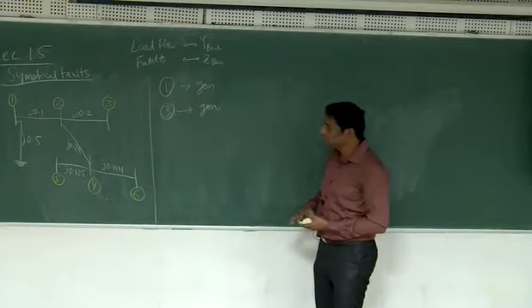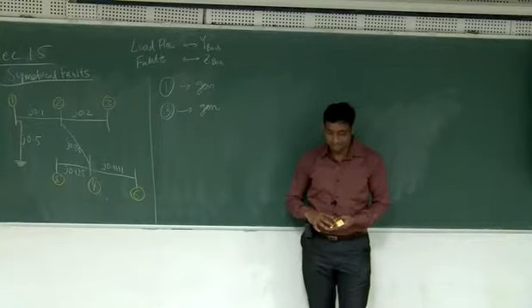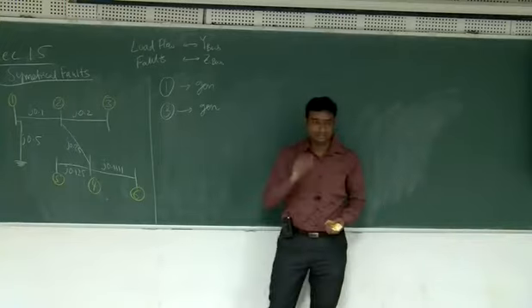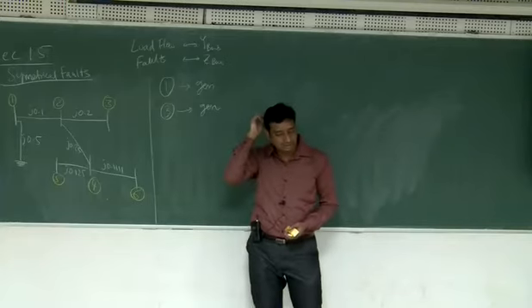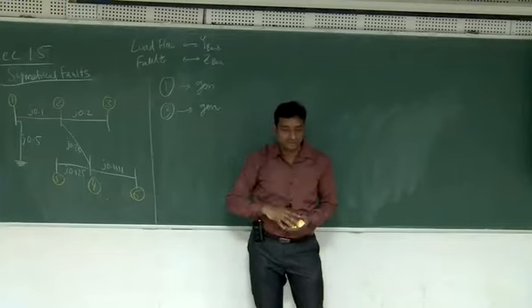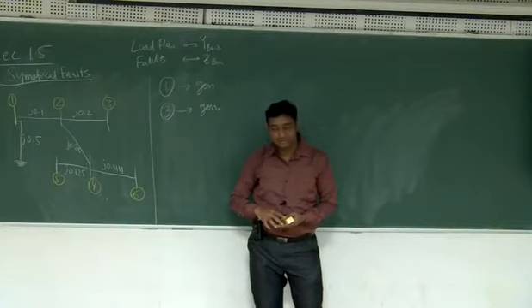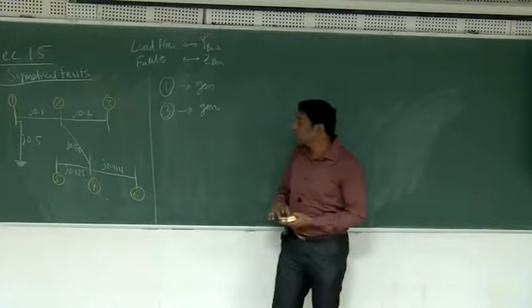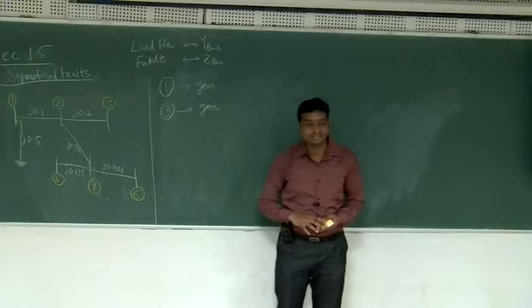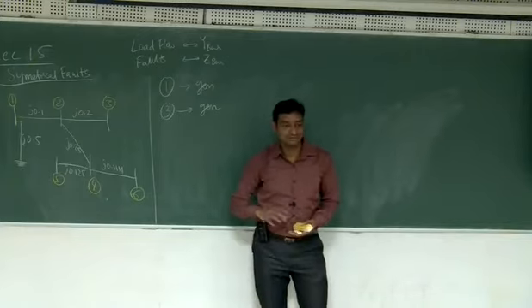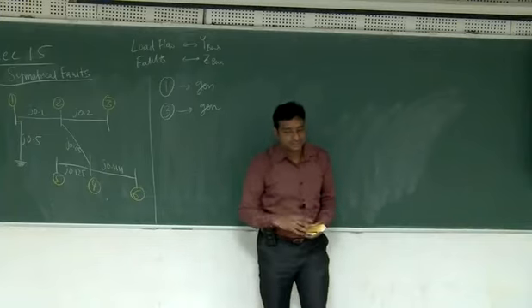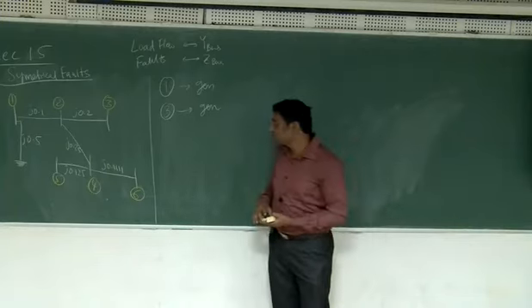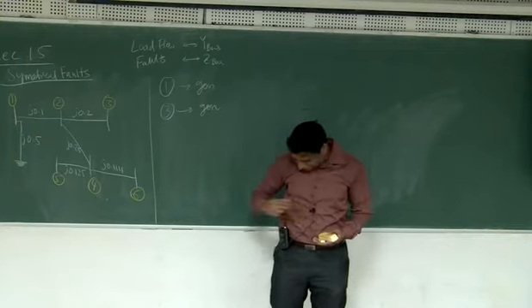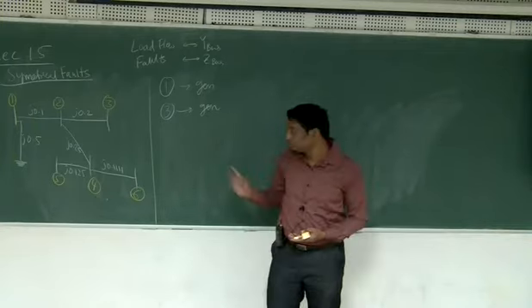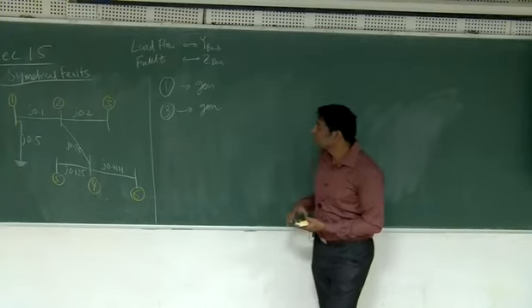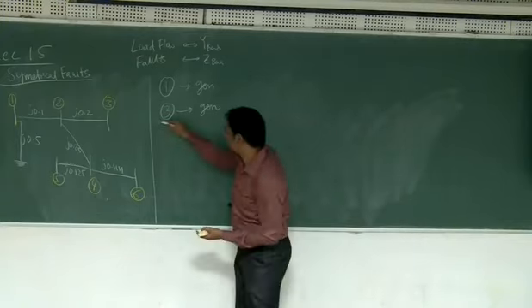Now the loads, because we are doing fault calculation, the fault current will usually be 3 times or 4 times or 5 times that of load current. So one convenient assumption that people make is that the base case currents are 0. So there are no loads and all these things, so that it is easy to do your calculation. But if you want to do the actual calculation, you need to also consider the load current. So I'll start with the problem directly.